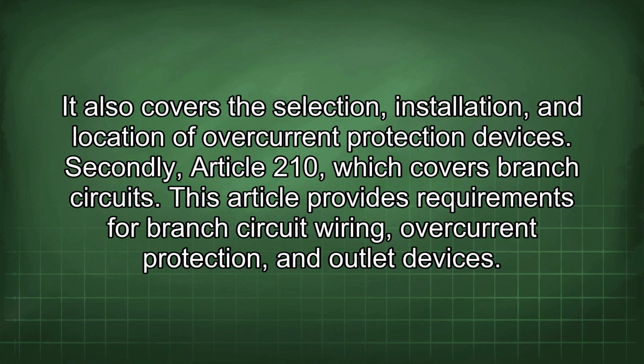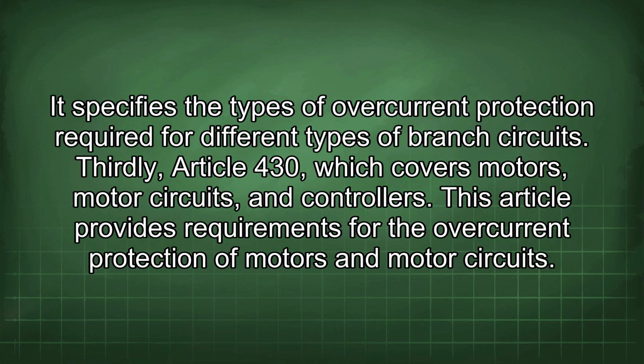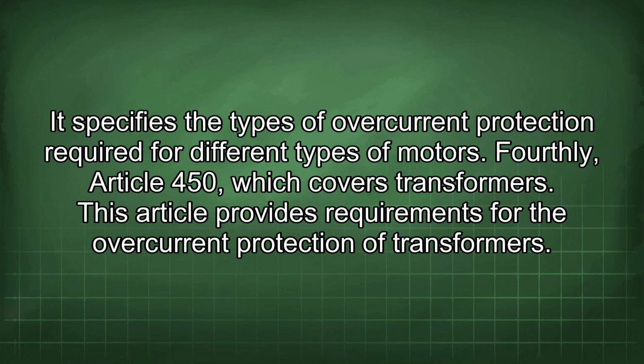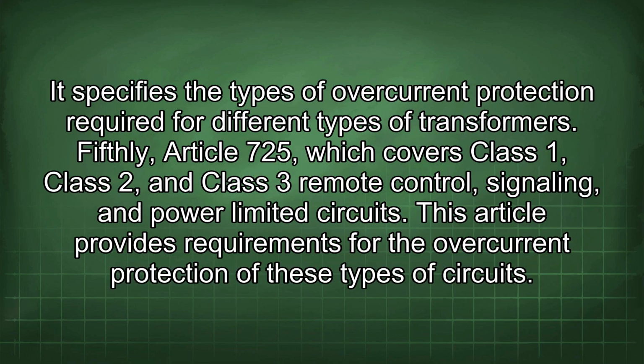Secondly, Article 210, which covers branch circuits. This article provides requirements for branch circuit wiring, overcurrent protection, and outlet devices. It specifies the type of overcurrent protection required for different types of branch circuits. Thirdly, Article 430, which covers motors, motor circuits, and controllers. This article provides requirements for the overcurrent protection of motors and motor circuits. It specifies the types of overcurrent protection required for different types of motors. Fourthly, Article 450, which covers transformers. This article provides requirements for the overcurrent protection of transformers. It specifies the types of overcurrent protection required for different types of transformers.